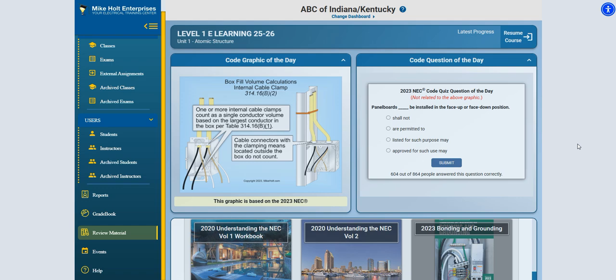On the right-hand side, it says panelboards blank be installed in the face up or face down position. And the options are shall not or permitted to, listed for such purpose. It is shall not. Panelboards shall not be installed in the face up or face down position. And I'll tell you where that comes from. If you happen to have your code book, you can look at Article 408.43. And I would also recommend when you attend these classes that you always have your code book with you.